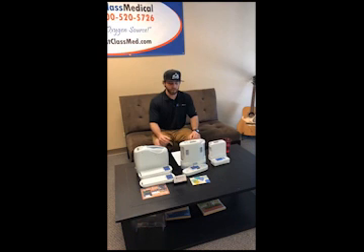Well, they've done a very good job at keeping them small, keeping them quiet, and giving everything they kind of want out of it. So, to go into the Inogen units, one of the biggest highlights with the Inogen models from the G2, G3, and G4 is the fact that they have an intelligent delivery system and sleep mode technology. What does that mean? So basically what's happening is, these are pulse flow concentrators.